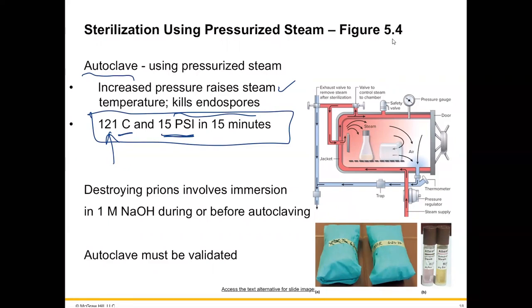Okay, so this is a picture of what's going on inside an autoclave. You're putting steam in, right? The steam is coming in, and there's a jacket around it, and that's going to also increase the pressure. I can find a video if you want to learn more about autoclaving. If you're worried about prions, you have to treat whatever you're going to autoclave with 1 molar sodium hydroxide before you autoclave it, or put it in the autoclave in the base. Autoclaving by itself does not get rid of prions.